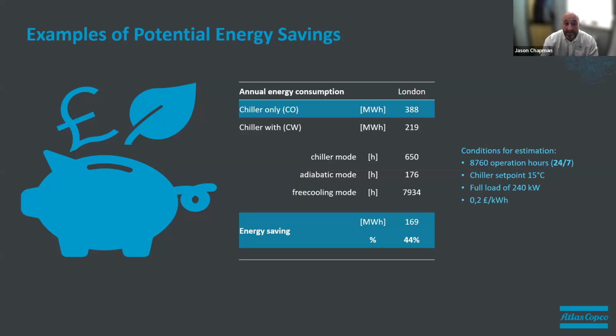And that's based on essentially 8,760 hours a year, running 24/7 on the system. So that is basically 44%. So nearly half of your energy spend on your cooling or chilling system can be reduced by using free cooling, using nature to the advantage.